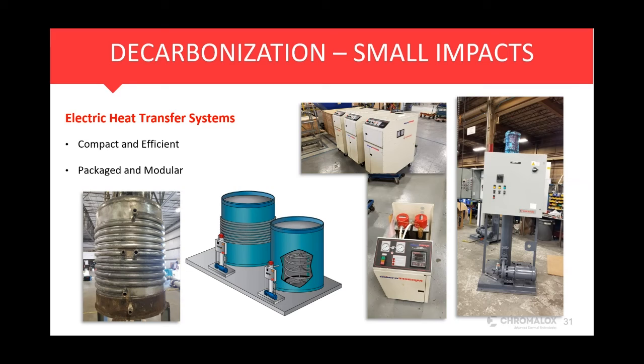This one—and we get this a lot—is indirect heating. So you'll have a heat exchanger, a jacketed vessel, especially in your chemical markets, your process facilities, process heating with heat transfer fluids. You can now take your large system offline and go with these small compact units that utilize electric heating technology here at Chromalox, adding a blower or a pump and your controls, all these nice packaged units that become modular. You now put them at point of use.